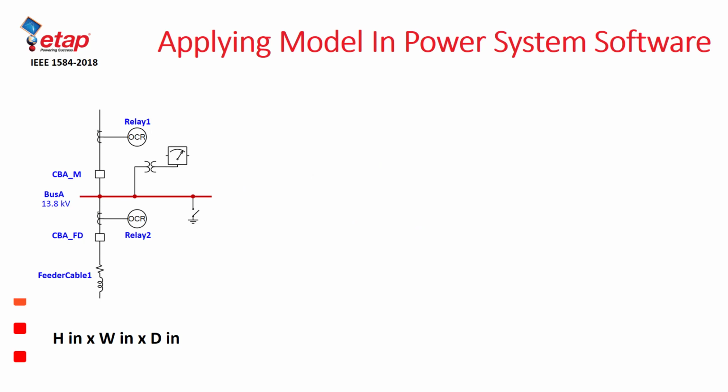As we can see on this particular slide, we have a representation of a medium voltage metal clad switchgear with two breakers, a source breaker and a load breaker. And as we can see, there is other equipment like potential transformers, PTs. There are instrumentation elements, which may also contain overcurrent relays.